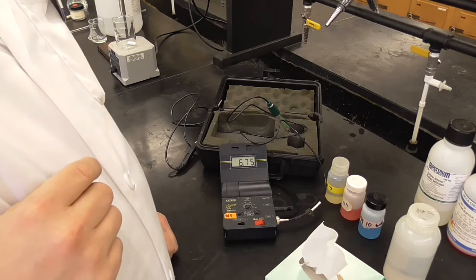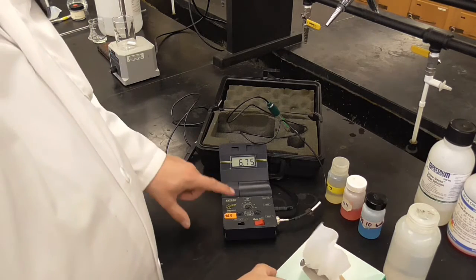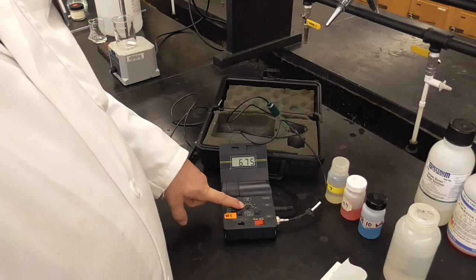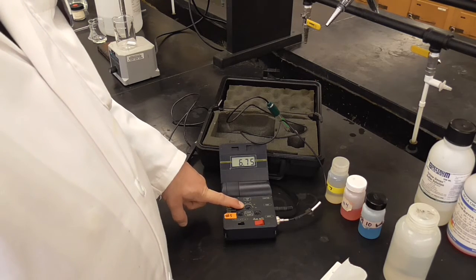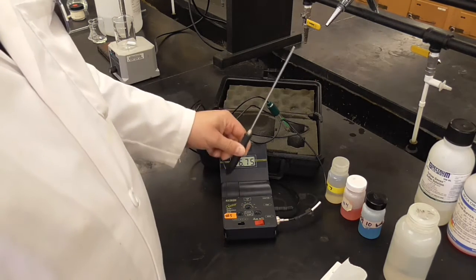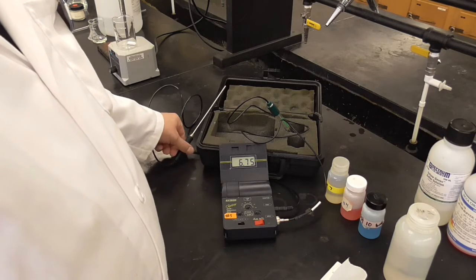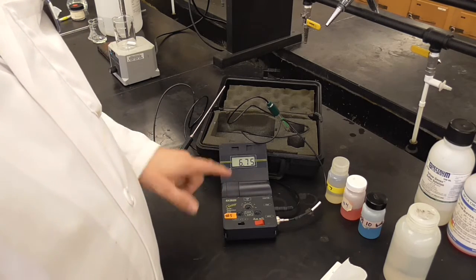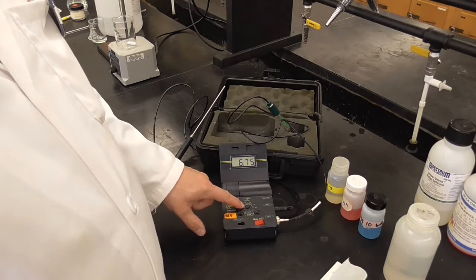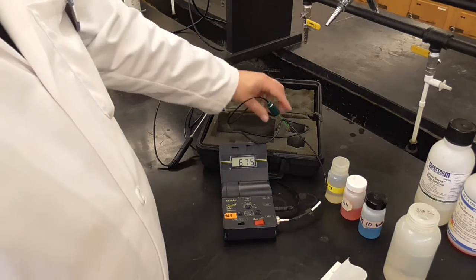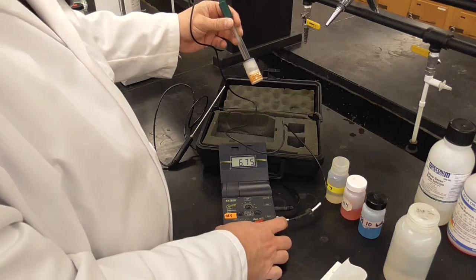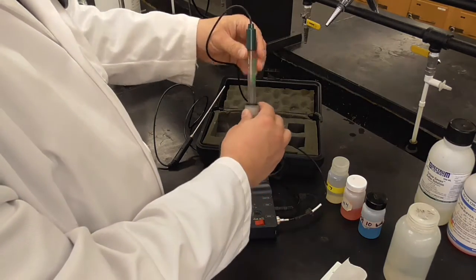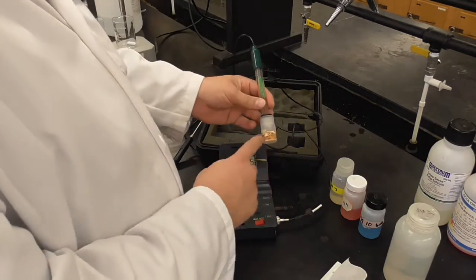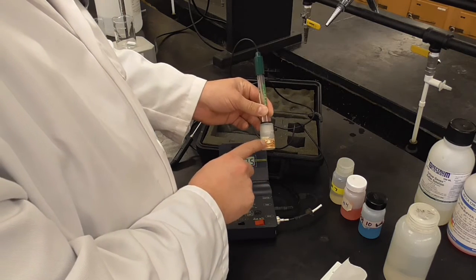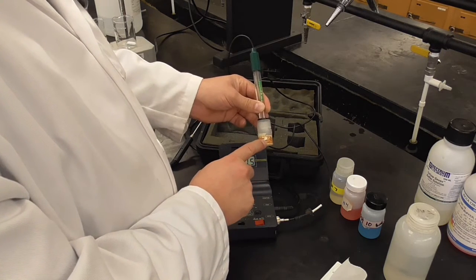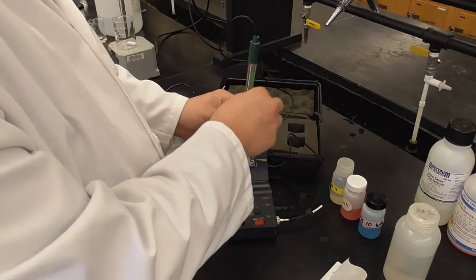Okay, so calibrating a pH meter. First you always double check that the temperature is at the appropriate spot. You can use the temperature probe attached if you wish, but usually as long as you're pretty close, it's pretty good because it's not that precise. Then I have my pH probe that I've attached. Make sure it's a good connection. Now the pH probe is kept in a storage solution, so I have to get it out of this little storage solution vial before I can do anything else.